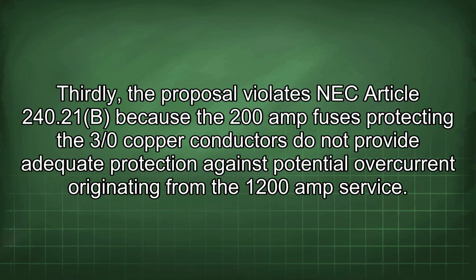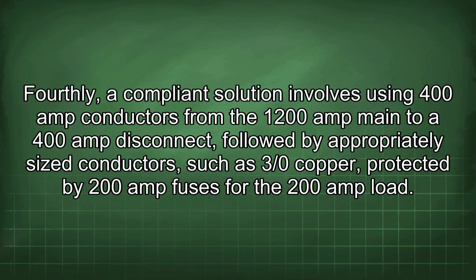Thirdly, the proposal violates NEC Article 240.21b because the 200 amp fuses protecting the 3/0 copper conductors do not provide adequate protection against potential overcurrent originating from the 1200 amp service. Fourthly, a compliance solution involves using 400 amp conductors from the 1200 amp main to a 400 amp disconnect, followed by appropriately sized conductors, such as 3/0 copper, protected by 200 amp fuses for the 200 amp load.